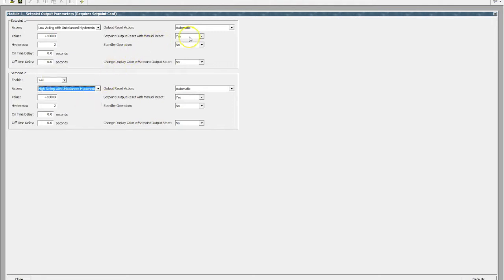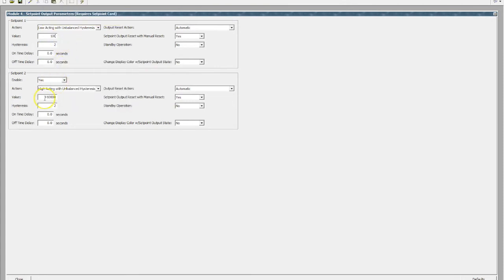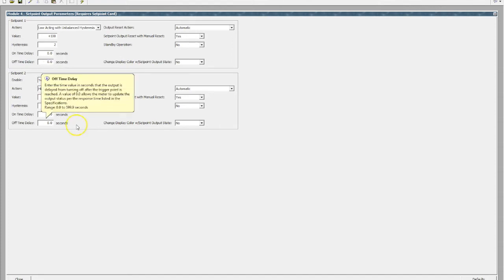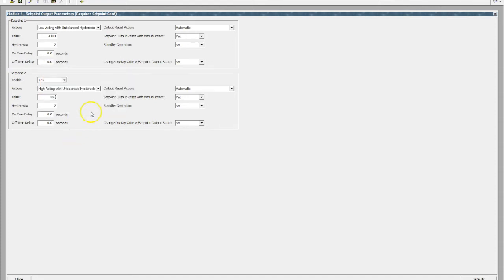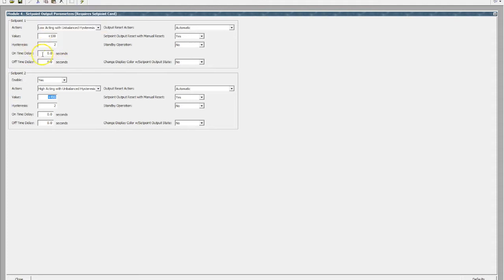For this particular case, the output reset will leave as automatic, and then we can nominate our value. So we might say we want a low alarm at 100 liters and a high alarm at 490 liters. We can have a programmed hysteresis and also an on and off delay time that just prevents flicker on your relay outputs.